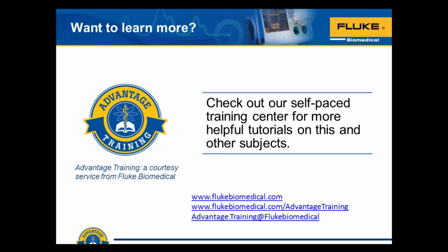There is no SI unit of measure for oximetry. It has no SI unit of measure that we can use to ensure the accuracy of the measurement. It is all determined based on clinical studies that are carried out as a requirement to get clearance to market from the FDA, to market in the United States, carried out by the manufacturer of that medical device. So there's really not too much in terms of adjustment that we can actually do to an oximeter that really produces a traceable measurement for us.